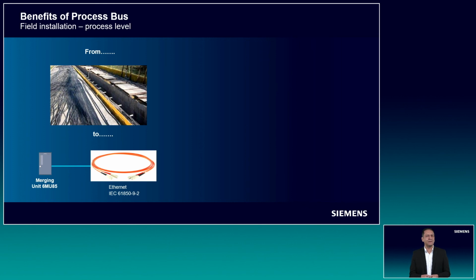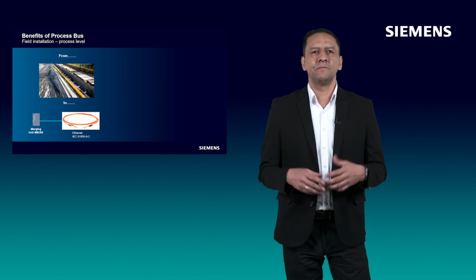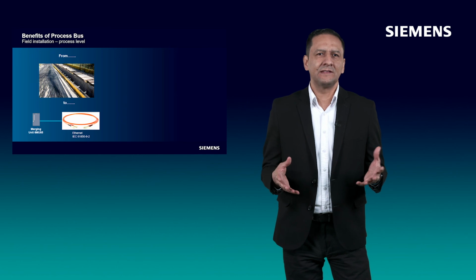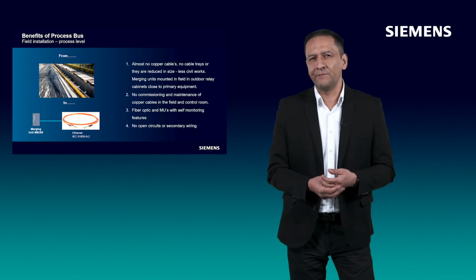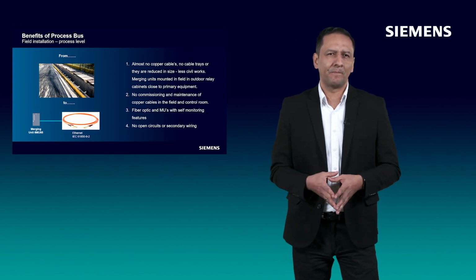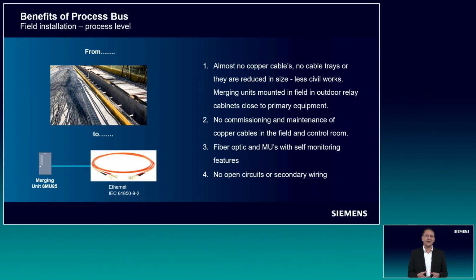Now, let's take a look at which optimizations could be achieved in the field. Because almost no copper cables are used anymore, we don't need such big cable trays as before. So they can be reduced in size or maybe even substituted with simple plastic pipes. It means we will need less material and civil works. Merging units should be mounted in the field, in existing primary equipment control cabinets, or separate outdoor relay cabinets close to the primary equipment. As we don't have copper cables in the field anymore, we don't have their commissioning and maintenance costs. Our substation becomes more reliable, as in case a fiber optic cable is damaged, it will be noticed immediately. Also, such a substation is safer to operate as we don't have secondary wiring in the control room anymore.